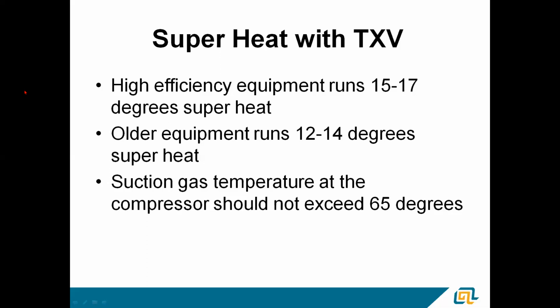Superheat has changed over the years. As the efficiency of the equipment has increased, they've tried to squeeze that superheat up a little bit higher. Right now, high efficiency equipment, I'm seeing 15 to 17 degrees of superheat is acceptable. And the older equipment, you'll run about 12 to 14 degrees of superheat.